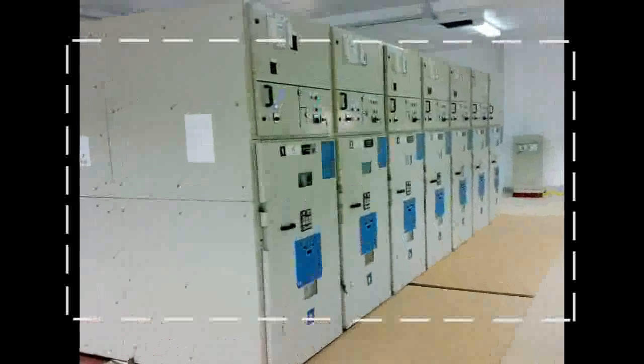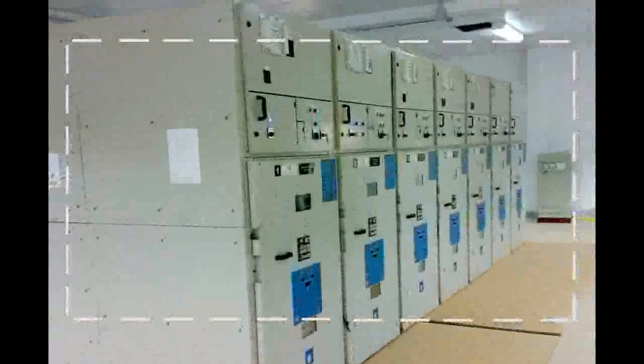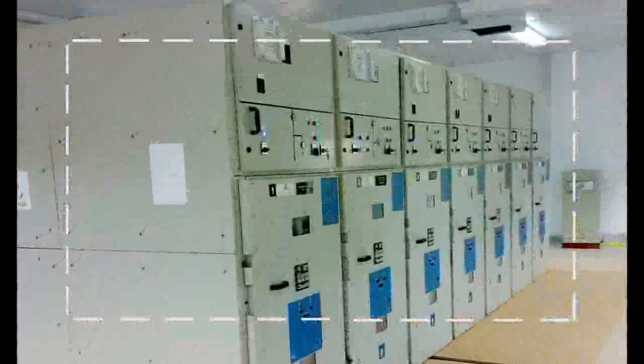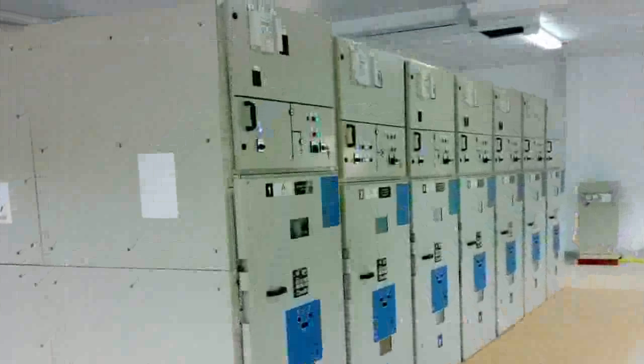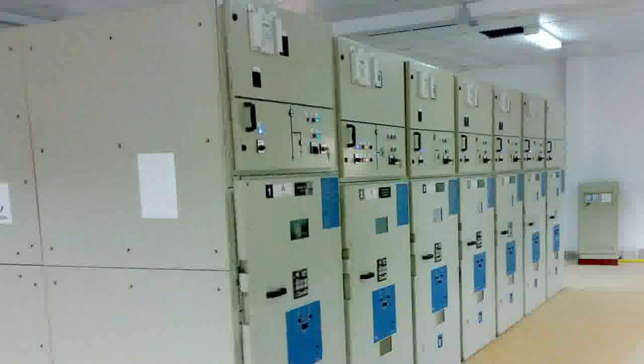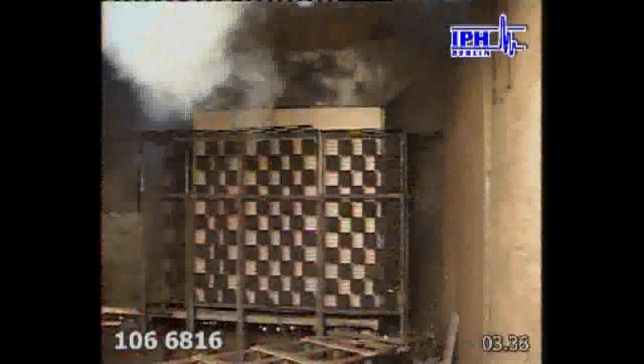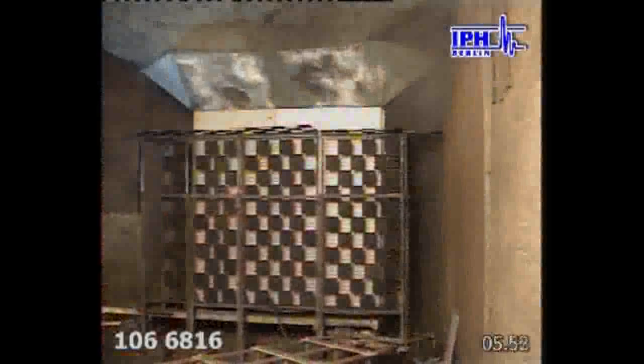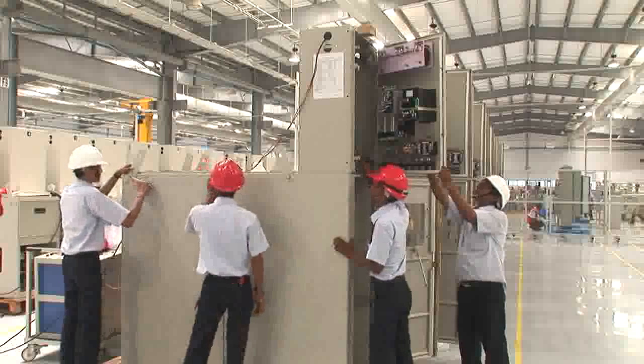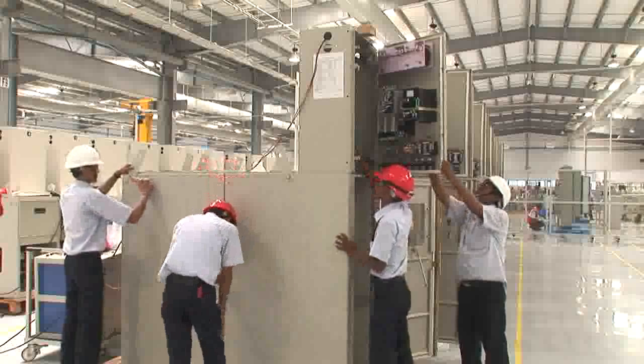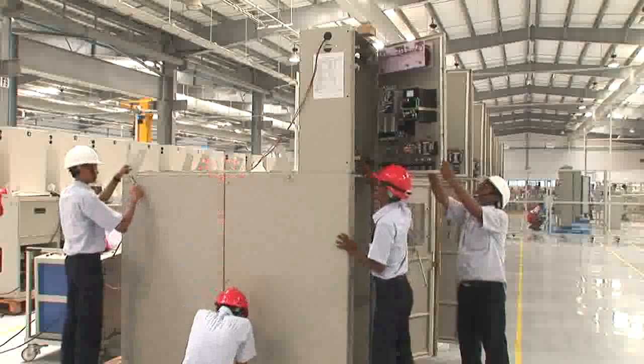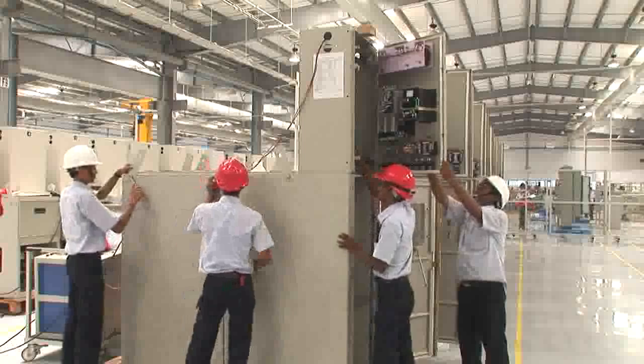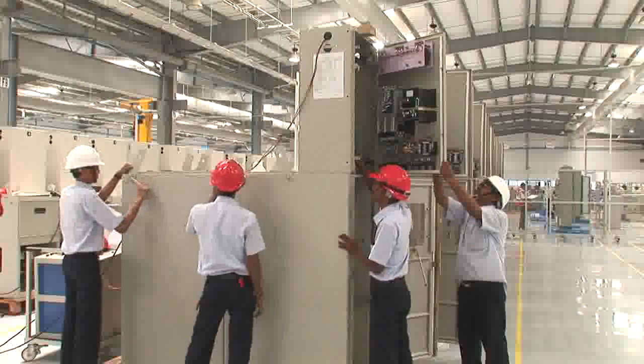The new standard demands that the room simulation should be done in a switchboard and may be placed under this simulated room, and only the extreme cubicle should be tested and not the middle one. This means that the cubicle is now not getting any support from the sides and is really withstanding the full pressure which would be required in case of fault occurring in the end cubicle. With these two changes, the situation alters completely, and now the enclosure is really subjected to the worst condition, and if it passes this test, then one gets the guarantee of operator safety even in the worst condition.